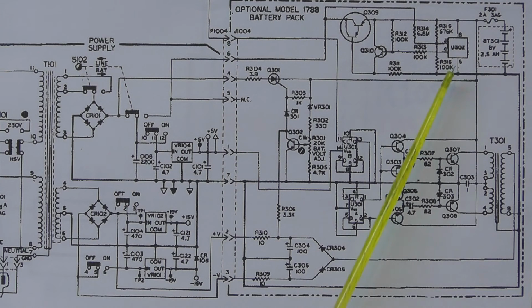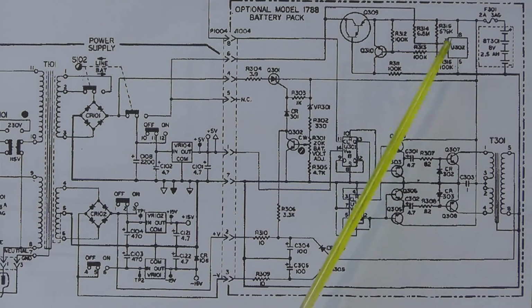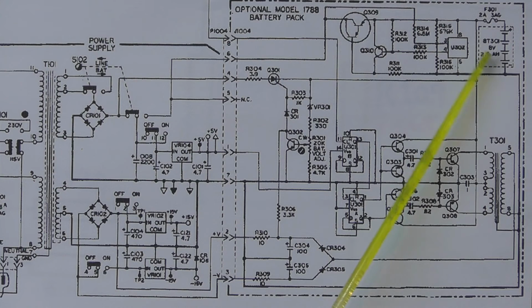The other protection we have for the battery is to prevent the battery from discharging to a low voltage which could damage the battery long term. So what we do here is that if the battery gets to a voltage less than 7.2 volts, we remove the battery from the meter. So we switch off the battery.